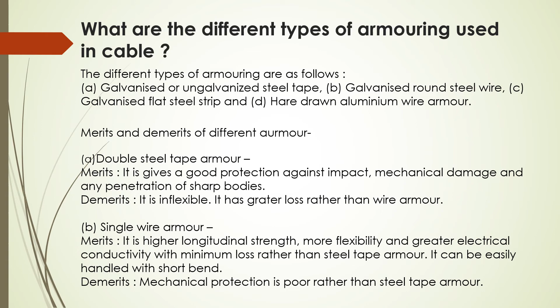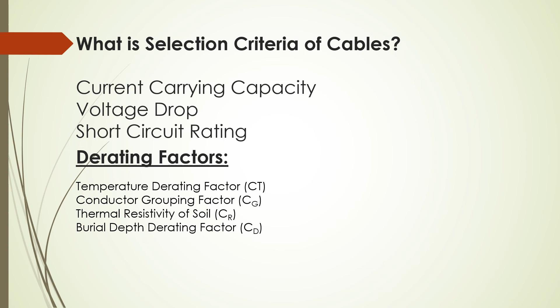What is the selection criteria for cables? The main selection points for the cable are current capacity, voltage drop, and short circuit rating. In addition to these, system voltage also defines the insulation of the cable. The cable sizing also depends on the type of the cable where it will be laid. So basically some derating factors are applied while selecting the size of cable. The derating factors are temperature derating factor, conductor grouping factor, thermal resistivity of soil, and burial depth derating factor.